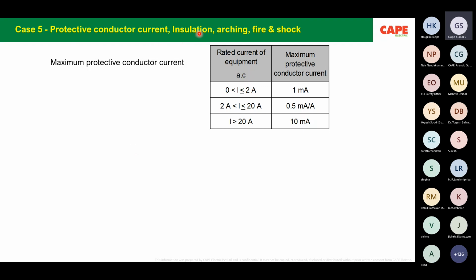Case 5, protective conductor current, insulation, arcing, and fire and shock. If you look even at the old regulations, the IE Rules 1956 or the Electricity Rules 1937, there was only one electrical safety requirement, which was the insulation resistance between live conductors and the earth. This means within the house, within the electrical installation, the minimum required insulation resistance between current carrying conductors and the earth is 1 megaohm. We are supposed to test it every 5 years, regulation number 30, and keep the record. But we were trying to escape from that. We were not really doing it.